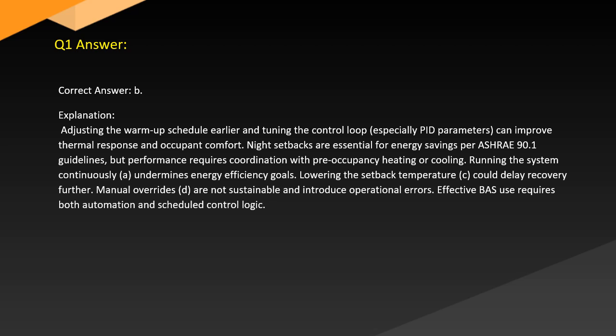Answer. Correct answer: B. Explanation. Adjusting the warm-up schedule earlier and tuning the control loop, especially PID parameters, can improve thermal response and occupant comfort. Night setbacks are essential for energy savings per ASHRAE 90.1 guidelines, but performance requires coordination with pre-occupancy heating or cooling.